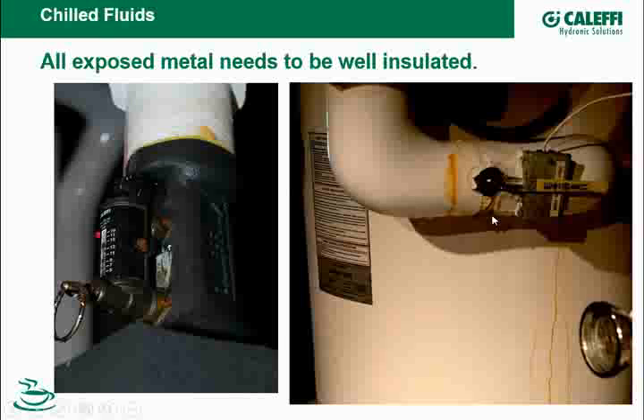But you can see what's happening here is it's obviously dripping off the bottom where these parts are sweating. And the same thing over here, I'm thinking that we needed to, we're going to go to a stainless steel screw. You can see the screws on this quick setter here have got a little bit of rust stain because they're carbon steel, and a little bit of dripping off the ring here.